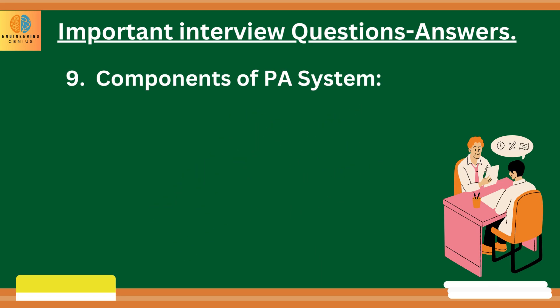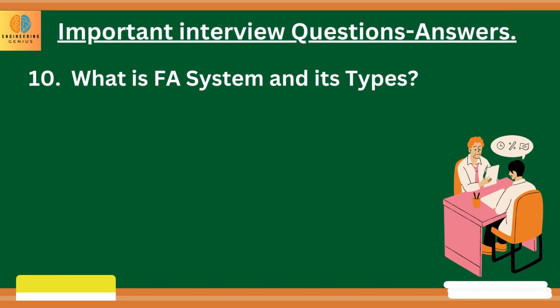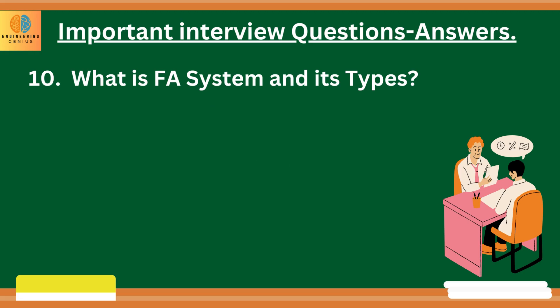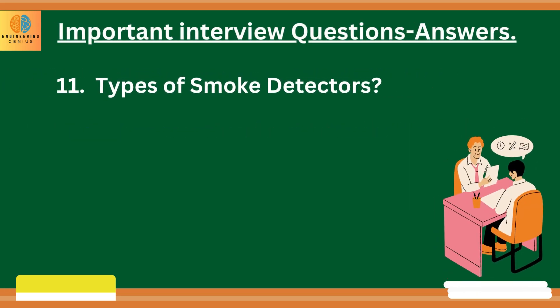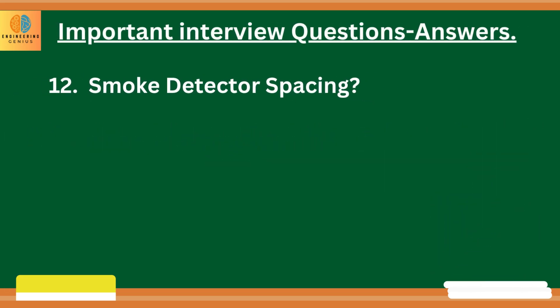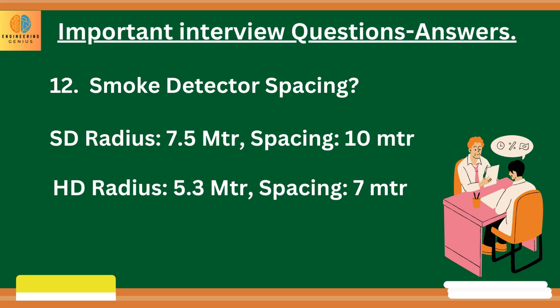If you want a detailed video on interview questions on public address system, do comment. The last question can be on fire alarm system: what is a fire alarm system and its types? A fire alarm system is a building system designed to detect and alert occupants and emergency forces of the presence of smoke, fire or any toxic gases. The two main types are conventional and addressable. There are three types of smoke detectors: ionization, photoelectric, and a dual combination of the two. Smoke detector radius is 7.5 meters and spacing between two smoke detectors is 10 meters. For heat detectors, the radius is 5.3 meters and spacing is 7 meters. For corridors, the maximum spacing can be 15 meters.